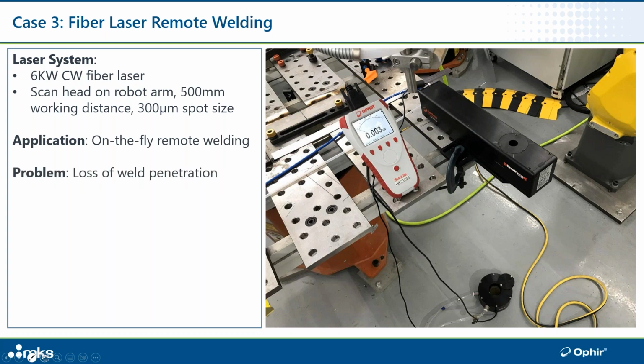The problem that this particular lab called me in on is that they were having loss of penetration of the weld. So they were turning the laser on, it was starting to penetrate fine, and then over the duration of this 4-second weld, it would lose penetration.